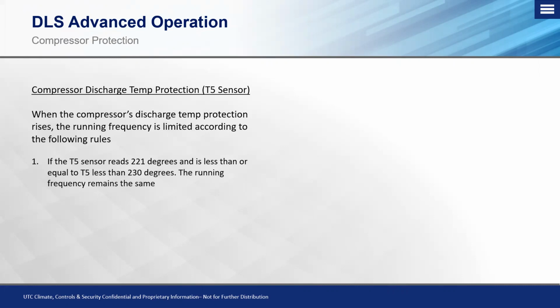Okay, so we look at the set of rules on there. If that T5 sensor, that discharge temperature protection sensor, reads 221 degrees and is less than or equal to the T5 less than 230 degrees. Okay, so if it's reading 221 degrees and it's less than 230 degrees, the running frequency of the compressor is not limited. It's fine. So essentially what this first bullet point is, if it's reading 221 degrees, it's not throwing any countermeasures. However, it does know that it is raising in temperature, but it has yet to throw a countermeasure to try to bring that down.